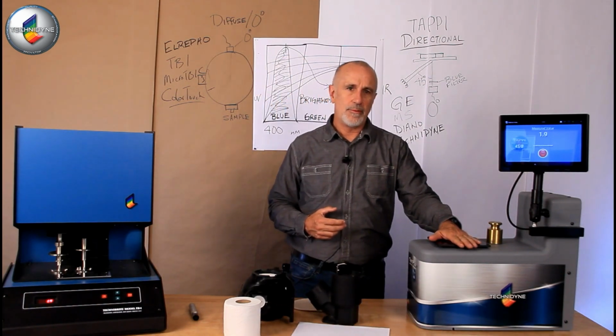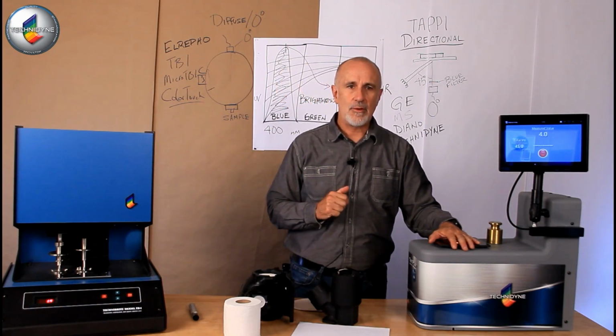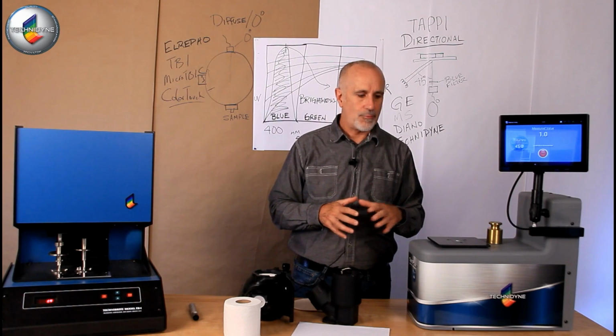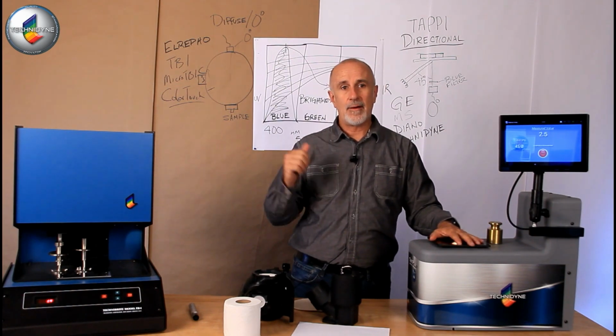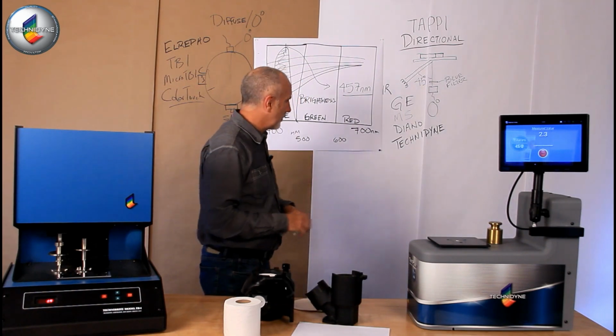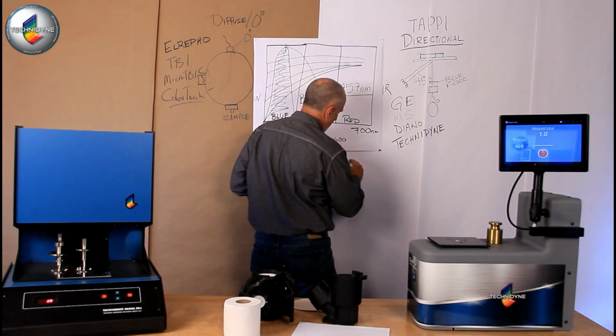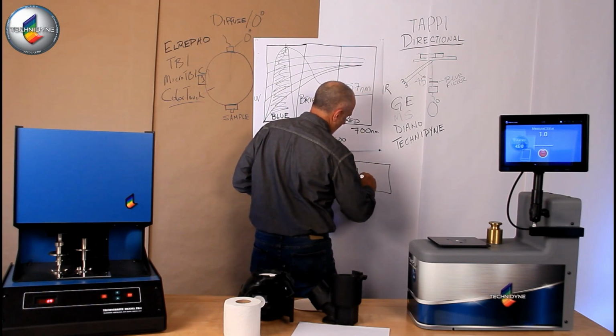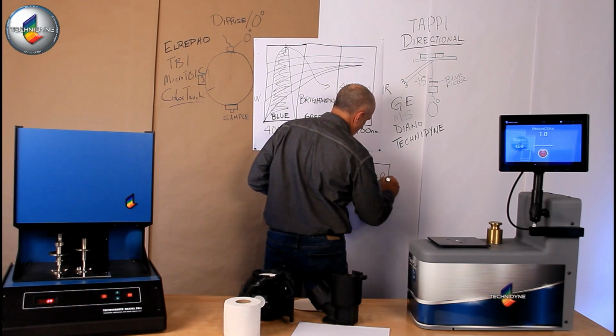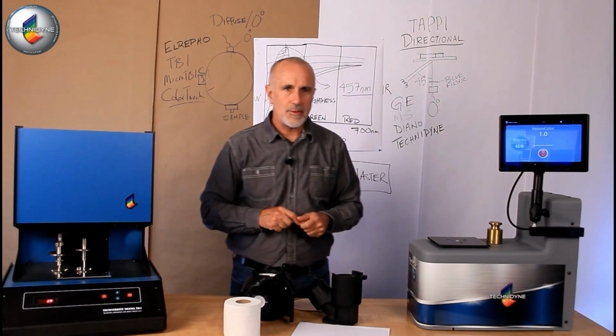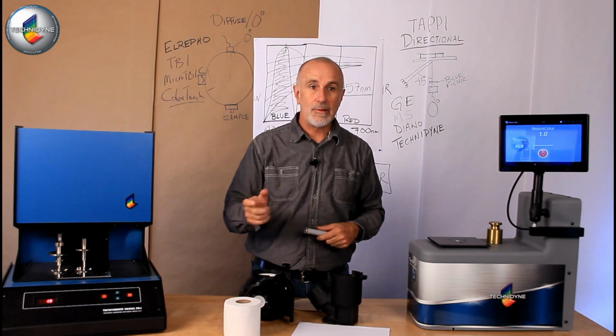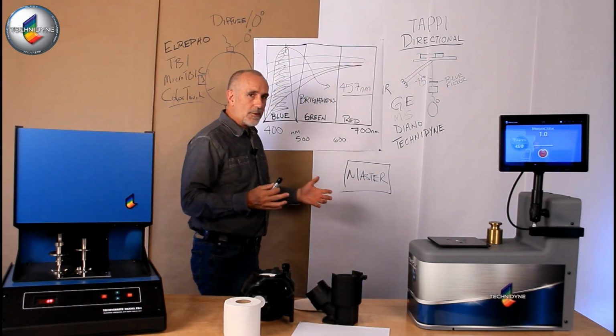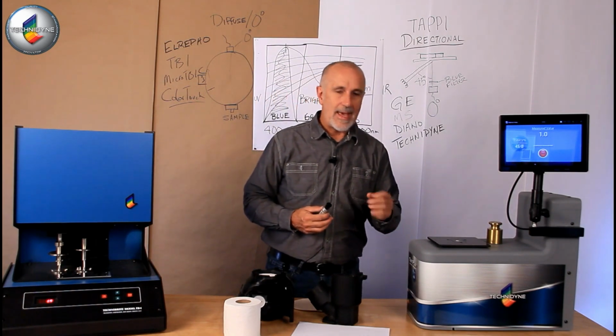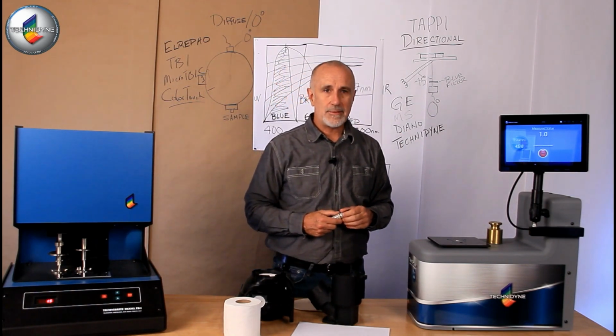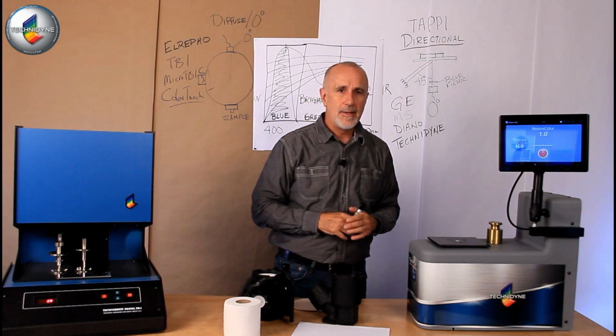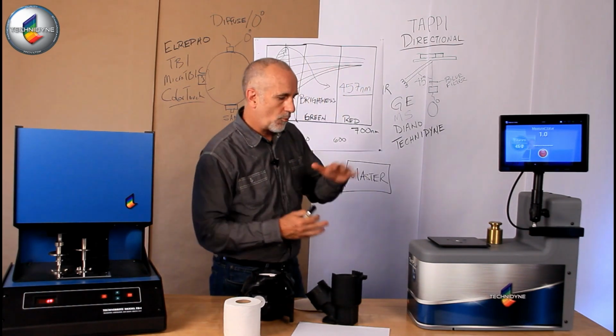For the TAPPI world, Technidyne Laboratory Services here in New Albany, Indiana, is the home for the calibration for the TAPPI brightness method. Back in our master's laboratory, we have master TAPPI instruments, and we have two of those that generate calibration standards. Those two are always brought together to make sure they're agreeing perfectly with one another. Then we have a stack of calibration standards in different ranges of brightness so that you can do a primary calibration and then verify your linearity of calibration across a wide range.